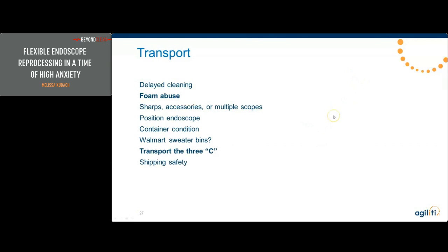There are foams made that have been studied that have a certain level of stasis, such that if you know cleaning is inevitably going to be delayed, you can use this foam to help keep the scope in good shape and moist until it can be cleaned, for an extensive length of time per the manufacturer. I know delayed cleaning of any sort is discouraged no matter what you're using, but I've seen a lot of facilities that are starting to use this as a part of their process, not as an inevitable consequence that they are trying to avoid. And that is worrisome because I think that is not going to be good overall in the long run.